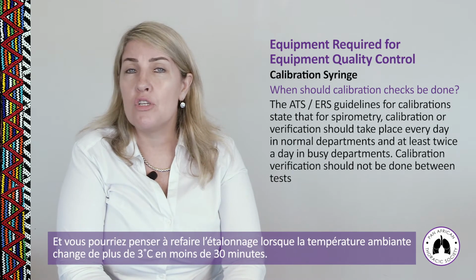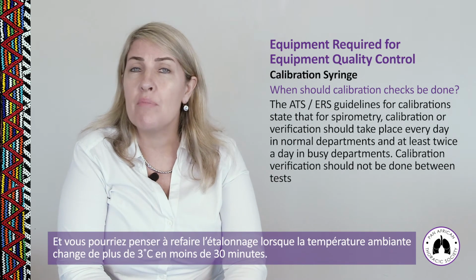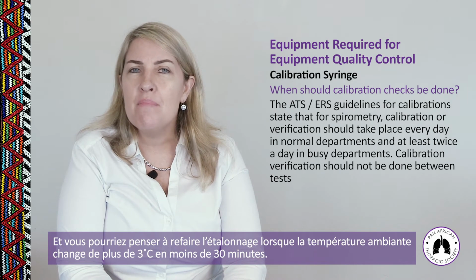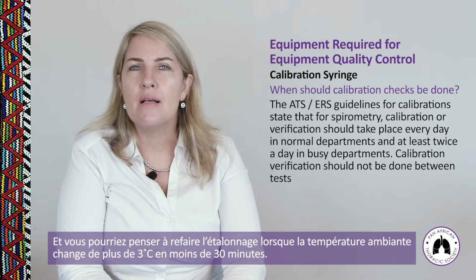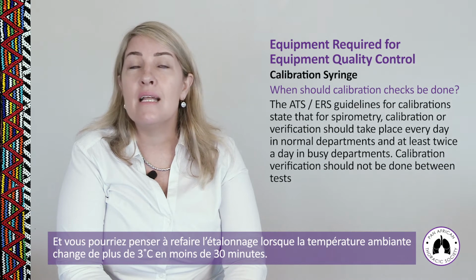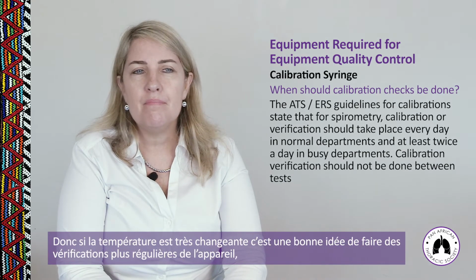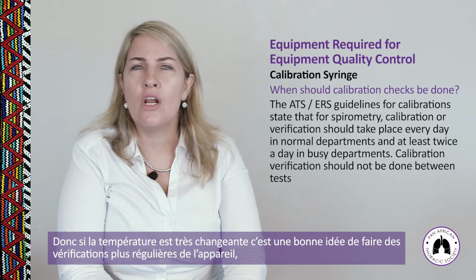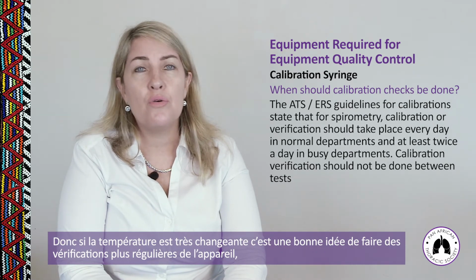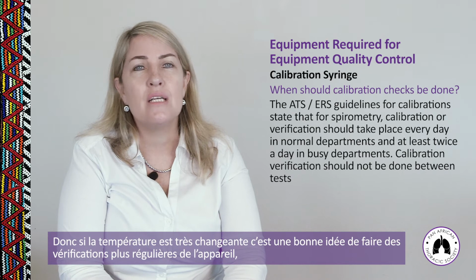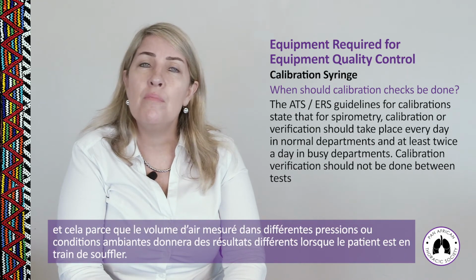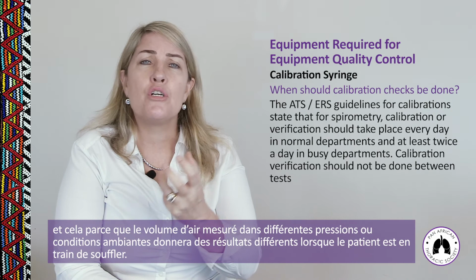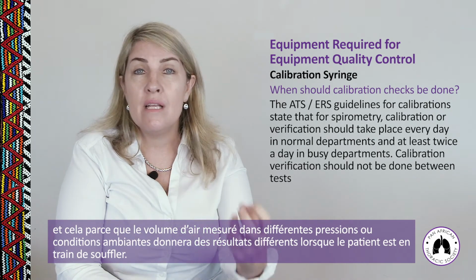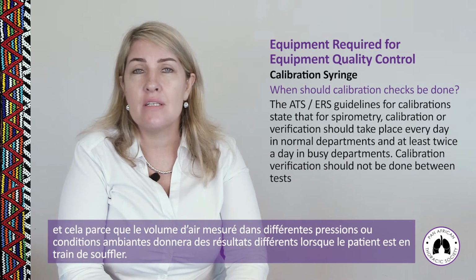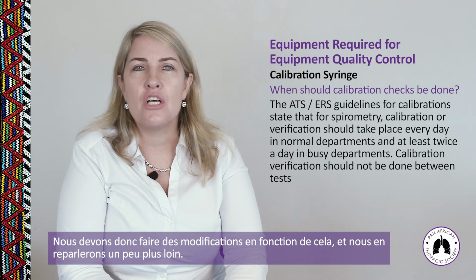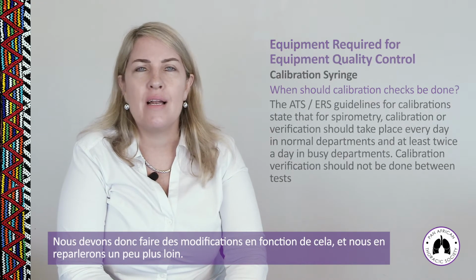Another time that you might want to consider redoing your calibration check is when the ambient conditions change in temperature by more than 3 degrees in 30 minutes. So if your temperature is fluctuating a lot, it's a good idea to make sure that you are rechecking the calibration of the machine. The reason for this is that the volume of air measured in different temperature, pressures and humidities will read the volume differently when the patient is actually blowing. So we need to make an adjustment for that, and a little bit more on that later.